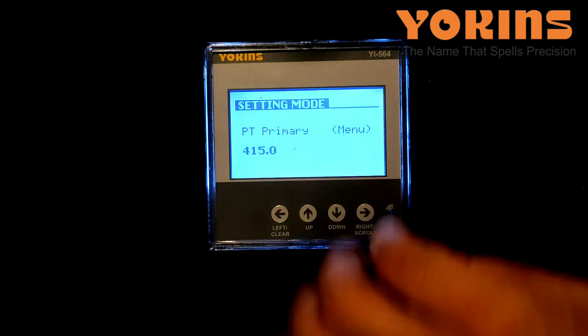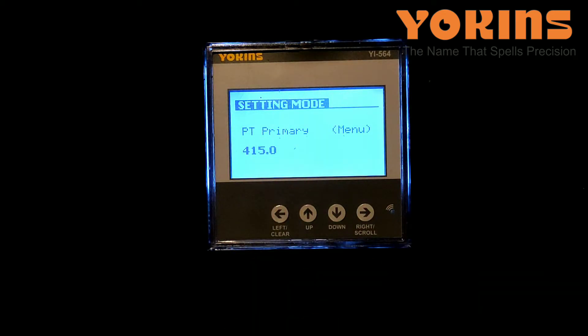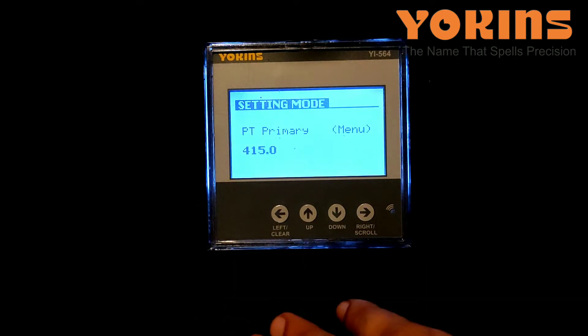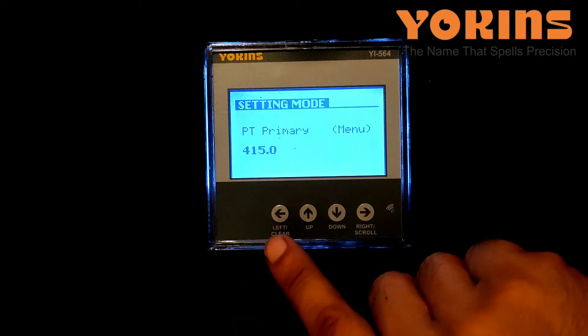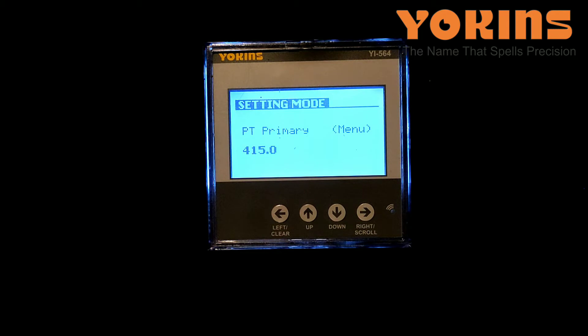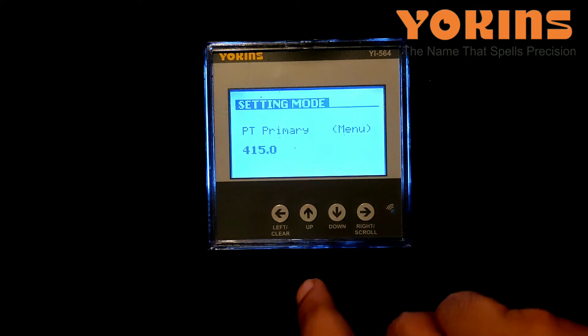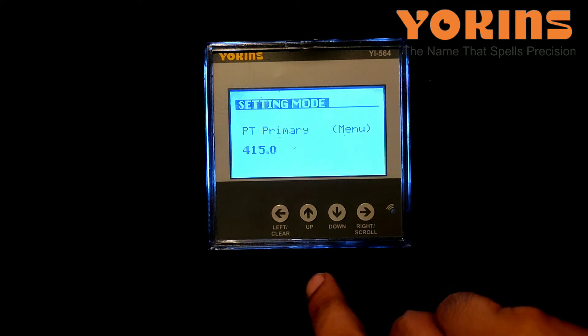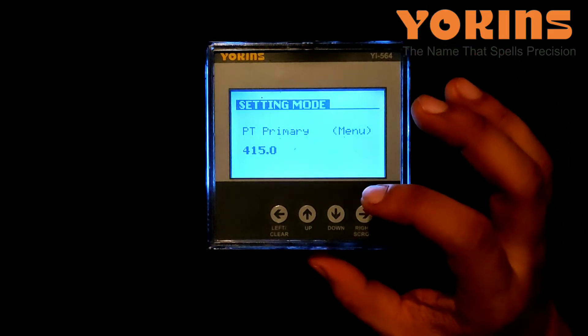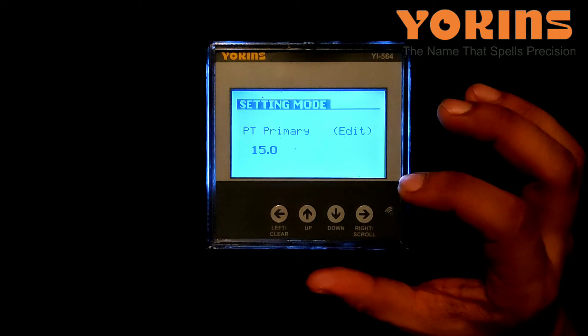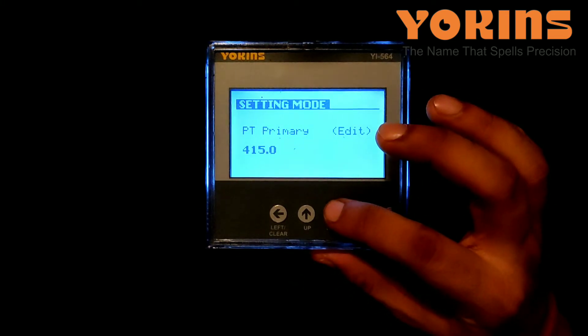Now we'll press the down button once to enter setting mode. It's showing PT primary: 415 — this is the default setting. If we are not using any PT, we need not change it. But if we are using a PT, we'll have to enter the primary PT ratio. For example, if we are using a PT of 11kV / 110V, we'll enter 11kV here. We'll press the right button and the first digit will start blinking.